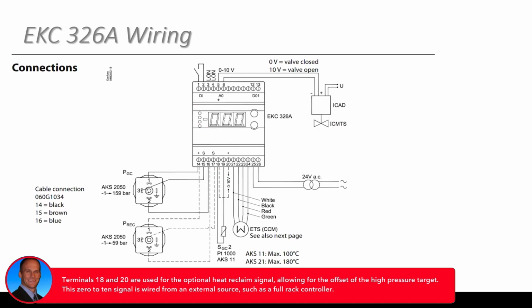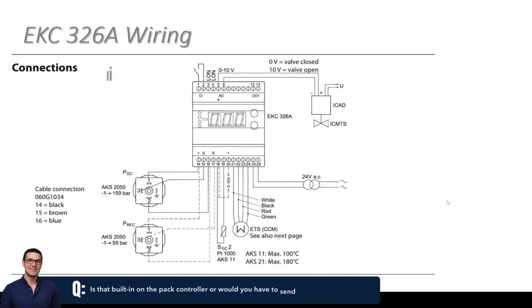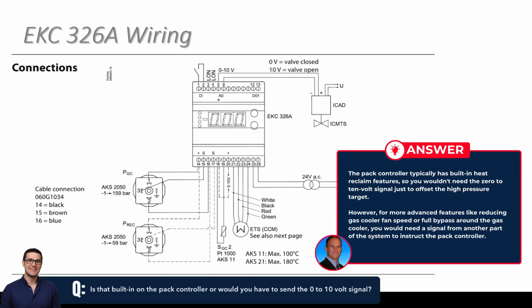And then we get into our receiver. That is built in on the pack controller, right? Or would you have to send a 0 to 10 volt signal? Pack controller, we've kind of gone a few steps further with heat reclaim. So if you just want to offset the high pressure target for heat reclaim, you typically wouldn't need this signal. But if you want to start to get into some of the more in-depth features we offer, as far as maybe starting to cut back your gas cooler fan speed, or if there's a full bypass piped in to go all the way around the gas cooler, then most of those applications you would need a similar input coming from another part of the system to tell the pack controller what to do. Fantastic. Cool. I'm excited to learn about that one.